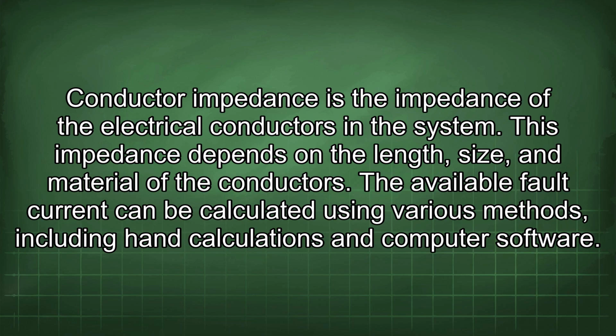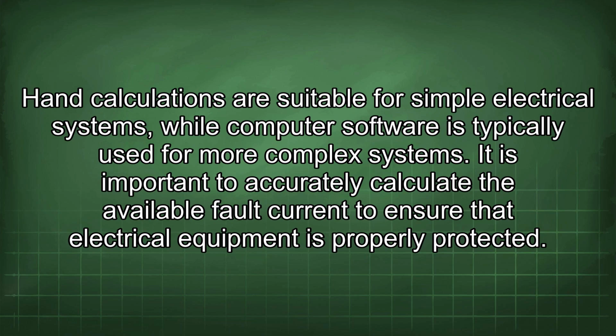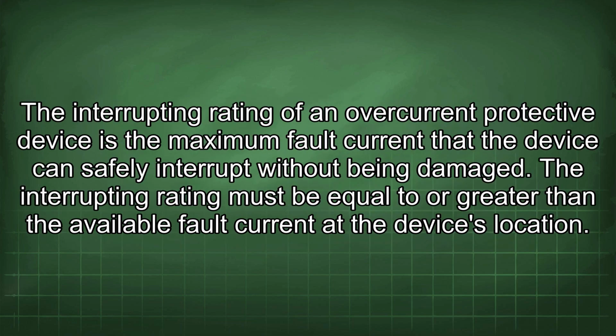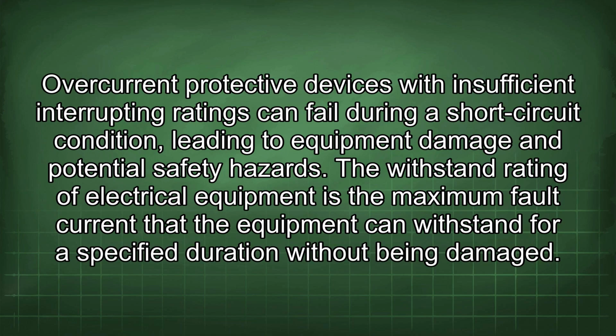The available fault current can be calculated using various methods, including hand calculations and computer software. Hand calculations are suitable for simple electrical systems, while computer software is typically used for more complex systems. It is important to accurately calculate the available fault current to ensure that electrical equipment is properly protected. The interrupting rating of an overcurrent protective device is the maximum fault current that the device can safely interrupt without being damaged. The interrupting rating must be equal to or greater than the available fault current at the device's location. Overcurrent protective devices with insufficient interrupting ratings can fail during a short-circuit condition, leading to equipment damage and potential safety hazards.